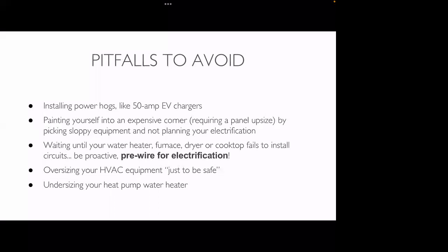On the other hand, for your heat pump water heater, we do recommend oversizing it, so don't undersize that. If you have a 40-gallon tank now, bump it up to 65 or maybe even 80 gallons if you're going to a heat pump water heater, because it takes longer to recover, so you want more hot water in storage. And it turns out the heat pump water heater tanks are now very well insulated, so you won't take a big hit on your bill by going to a bigger tank. That used to be true in the past when the insulation wasn't as good.